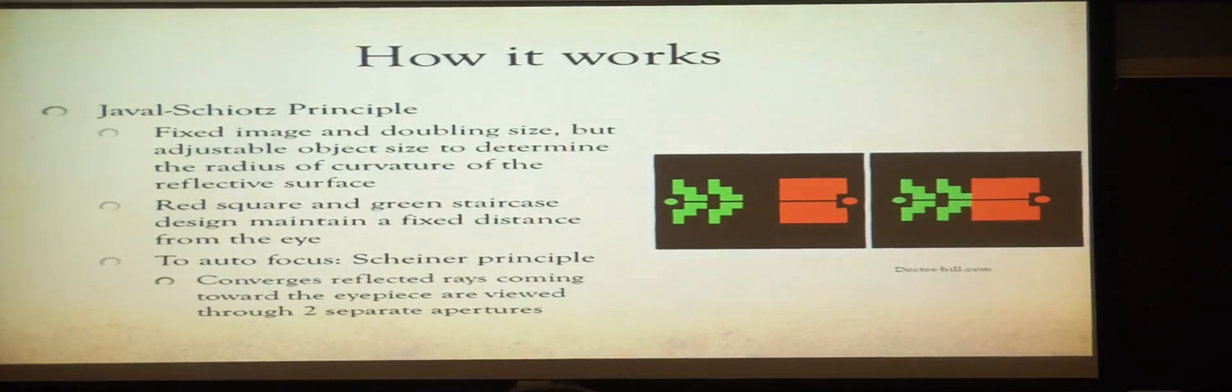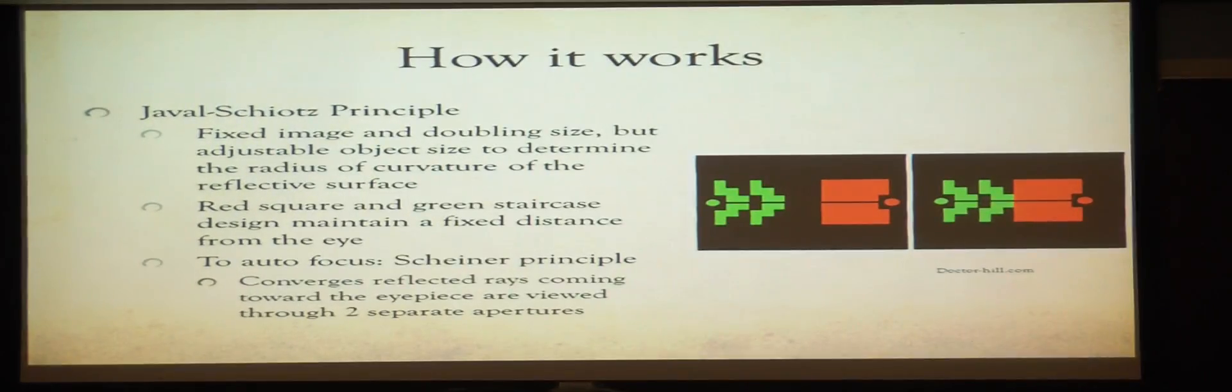The keratometer has two different types. The first one being the Javal-Schiotz principle, where there's a fixed image of fixed doubling size, and the object size is adjustable to determine the radius of curvature of the reflective surface. It will use a red square and green staircase to maintain a fixed distance from the eye, and it applies the Scheiner principle which is used to auto-focus the image, and this converges to reflect the radius into one focal point so that you can see it through the eyepiece.